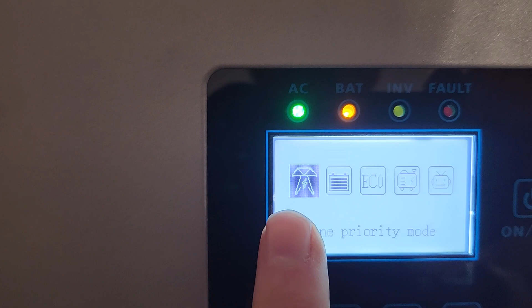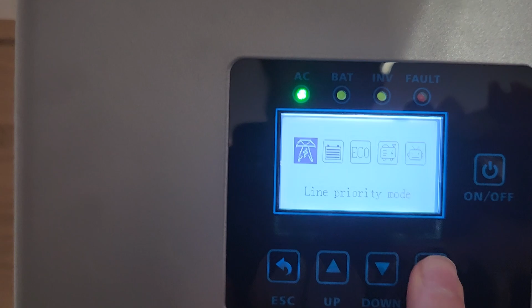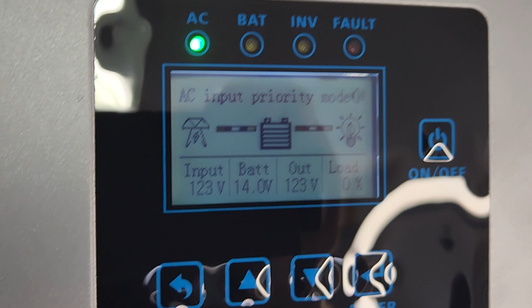Your system settings should be line priority, so it defaults to the AC and then rolls to battery backup. Don't worry about any of the other settings. This is in input priority mode. The battery is charging - it's at 14 volts and climbing right now.